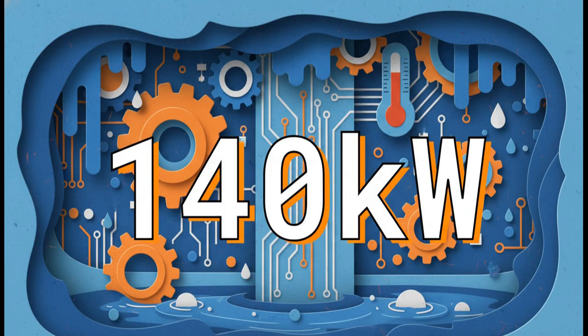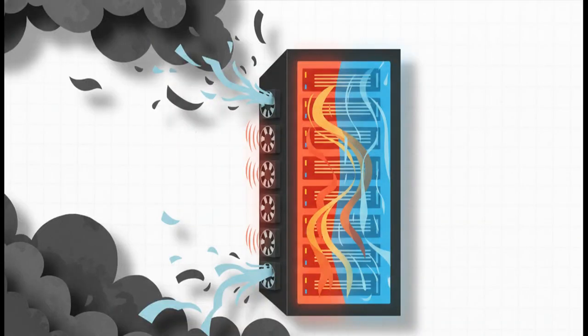140 kilowatts — just let that number sink in for a second. That's how much cooling power you need for a single server rack running NVIDIA's newest AI chips. That's an absolutely insane amount of heat packed into a tiny space. There's no way, zero way, to cool that with air. It's a hard physical limit.